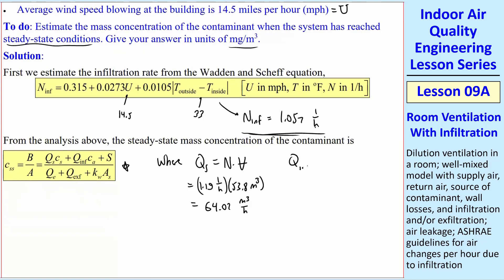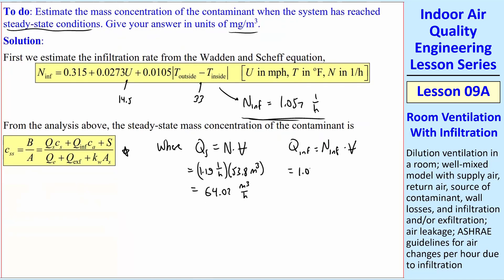And then Q infiltration is N infiltration times V, 1.057, one over hours, times 53.8 meter cubed. And that becomes 56.87 meter cubed per hour.